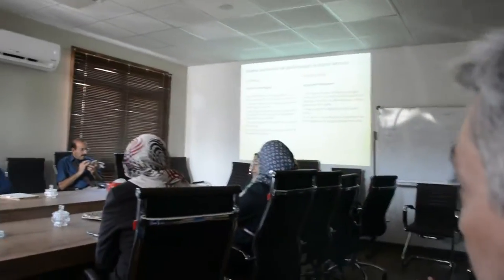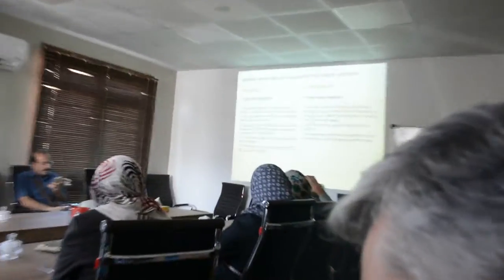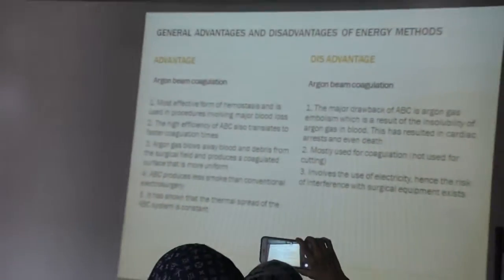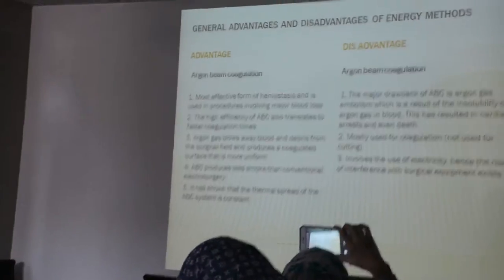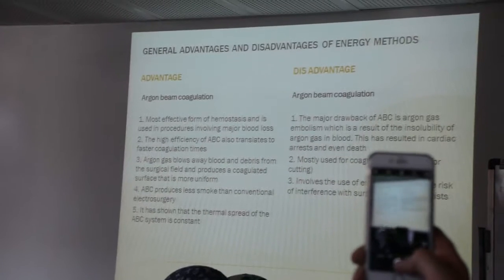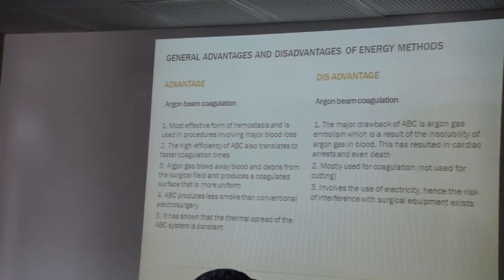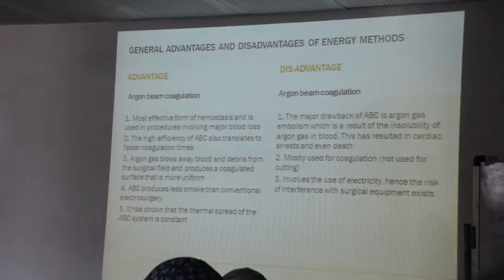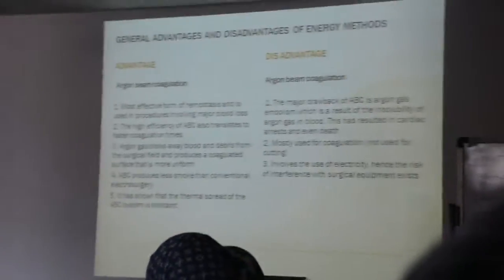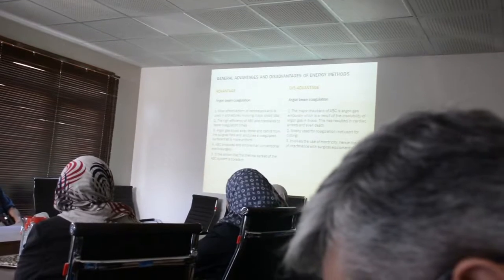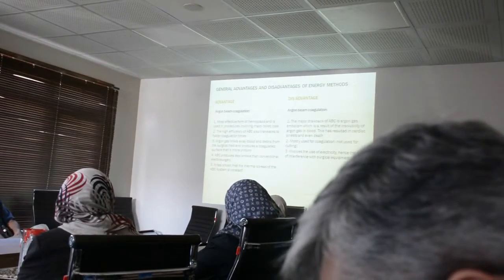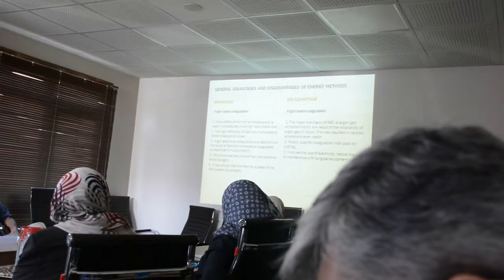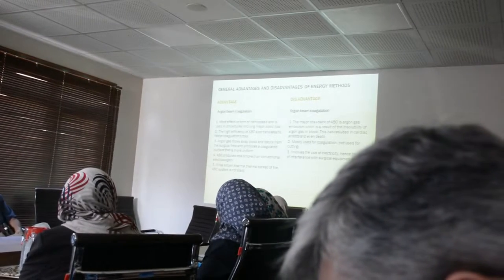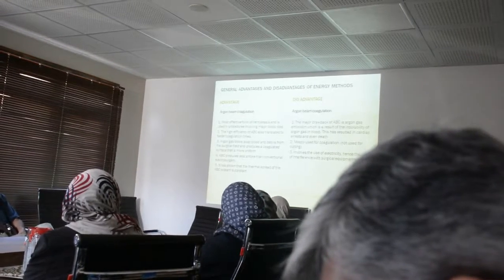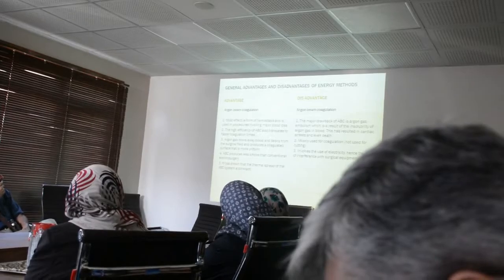Advantage of argon beam coagulation: most effective for hemostasis and used in procedures involving major blood loss. The high efficiency of argon beam coagulation also translates to faster coagulation times. Argon gas blows away blood and debris from the surgical field and produces a more uniform coagulated surface. It produces less smoke than conventional electrosurgery. It has been shown that the thermal spread of the argon beam coagulation system is constant.